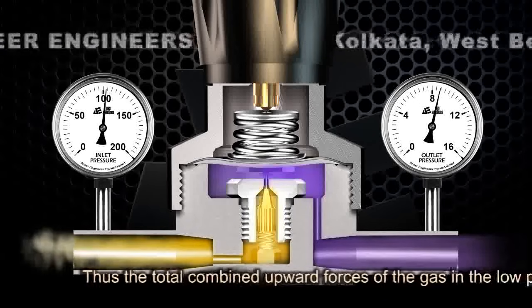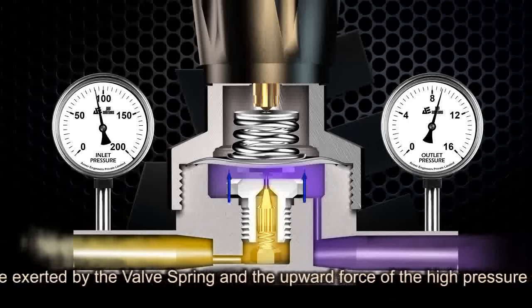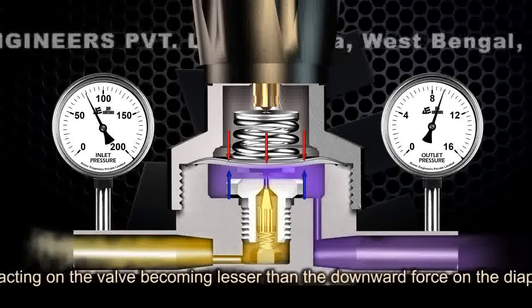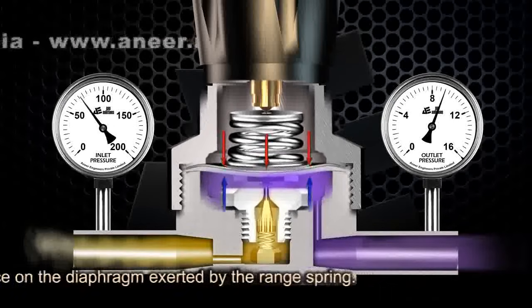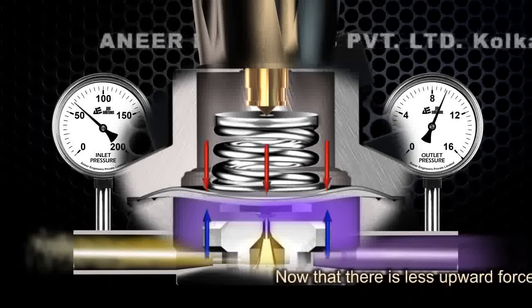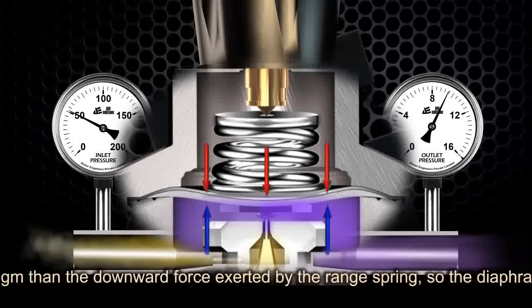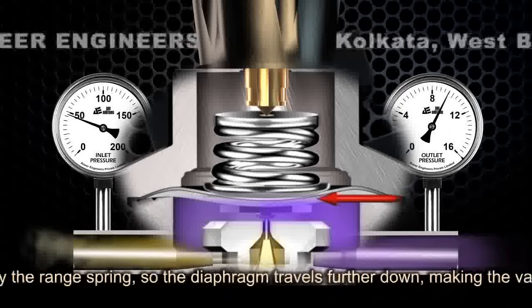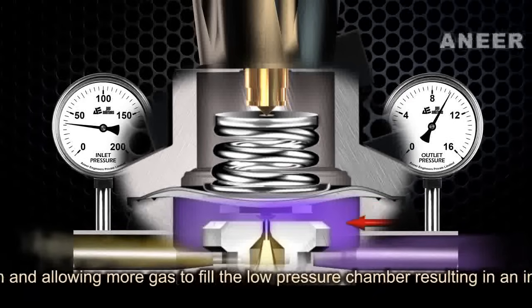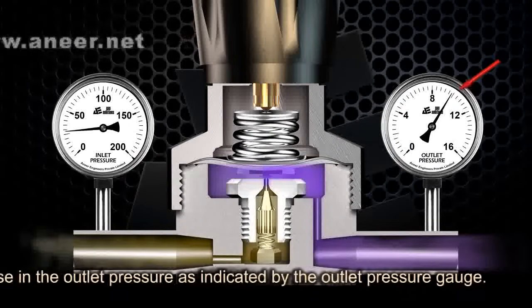Thus, the total combined upward forces — the gas in the low pressure chamber, the upward force exerted by the valve spring, and the upward force of the high pressure gas in the valve chamber acting on the valve — become lesser than the downward force on the diaphragm exerted by the range spring. Now that there is less upward force on the diaphragm, it travels farther down, making the valve open further and allowing more gas to fill the low pressure chamber, resulting in an increase in the outlet pressure as indicated by the outlet pressure gauge.